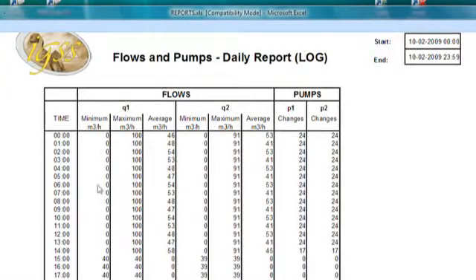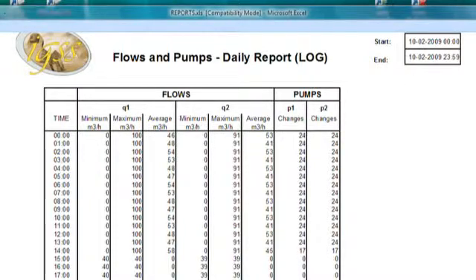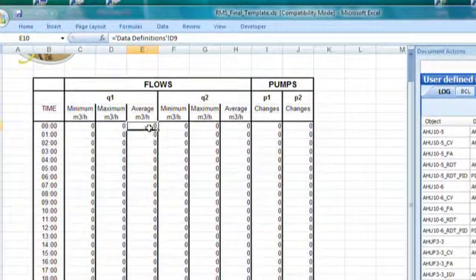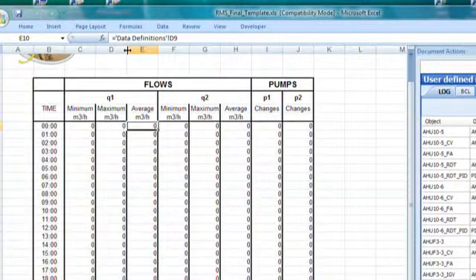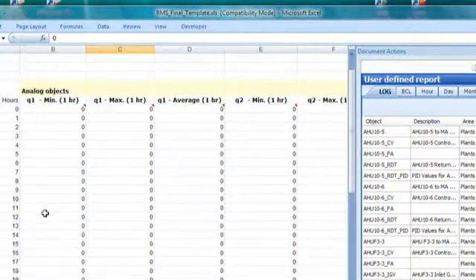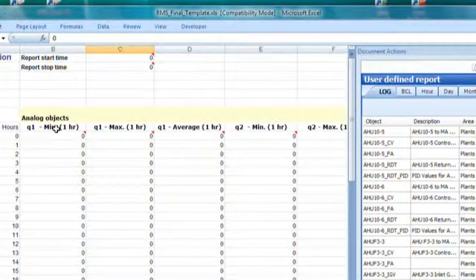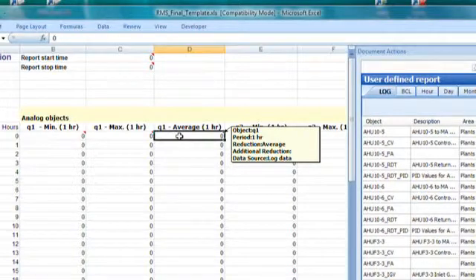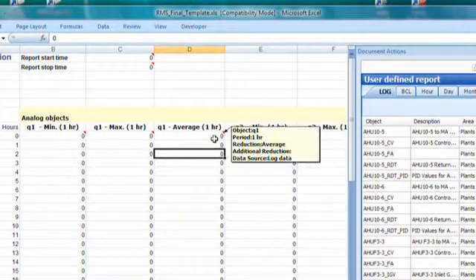If we zoom in on this report, we can see all the values on screen. I will go in and manipulate the value 46, as you see under Q1 average. When we click the cell where the value 46 came up, we can see that it's actually a cell reference in Excel — data definitions D9, that's the cell it refers to. So that's where I have my RMS tag in IGSS. I go to the data definition sheet and move to the top where I have my flow meters. I go to the cell Q1 average, and you can see a small red triangle — that's an Excel comment.